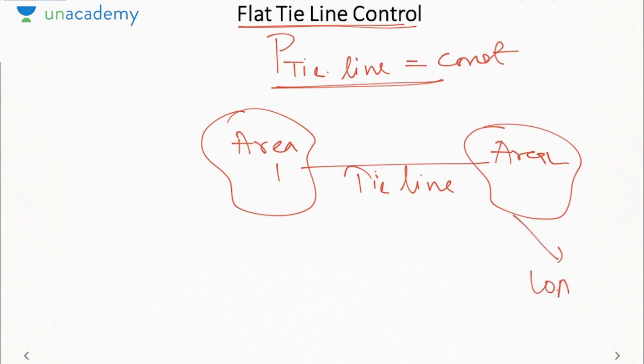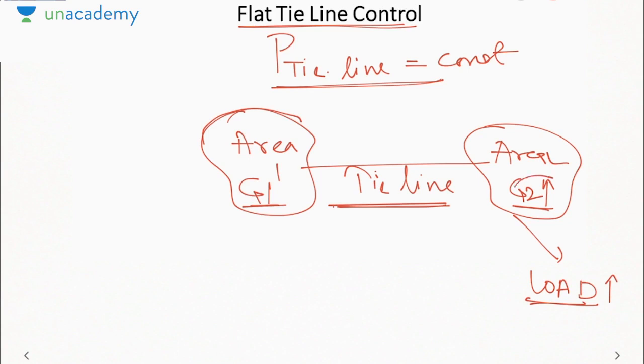If load here increases, then the generator here must share the increased load. No generator in area 1 should be affected. That way there will be no additional power flow through the tie line. Whatever is the power that is being transferred through the tie line will remain constant. Otherwise, if generator 1 also was sharing the load, then it will transfer that additional power to G2. So tie line power will also increase. That is called as flat tie line control. So wherever the load increases, that generator will take care of the load.